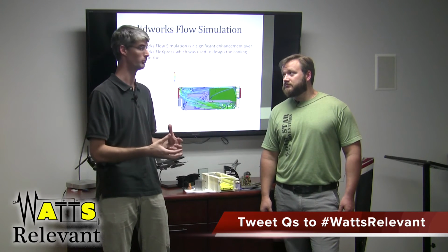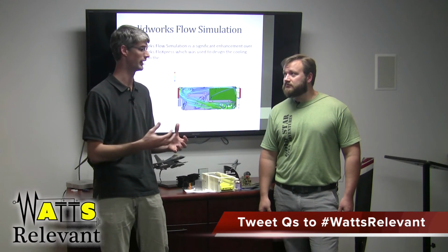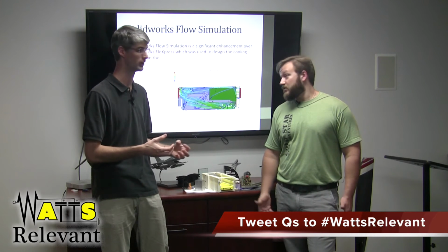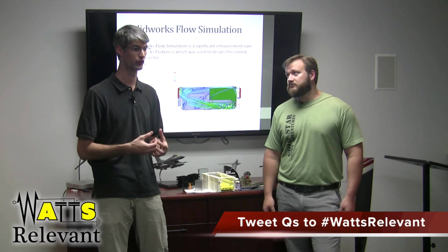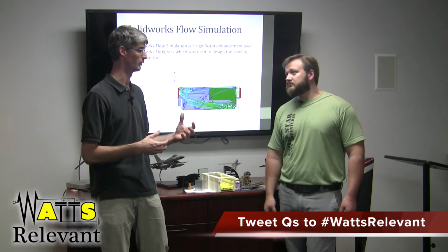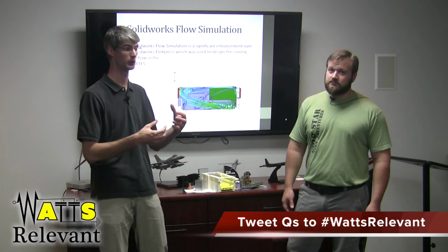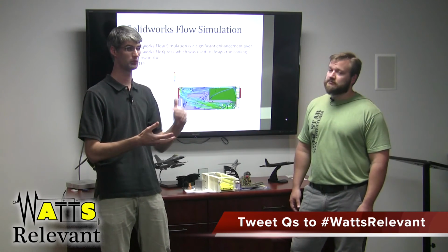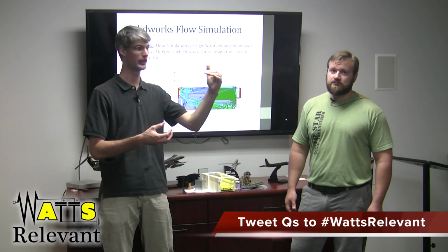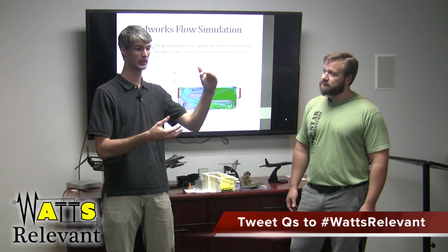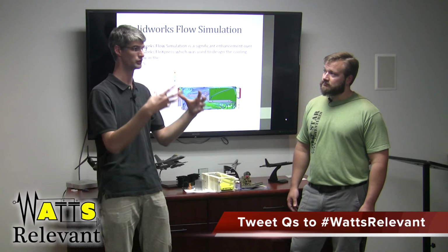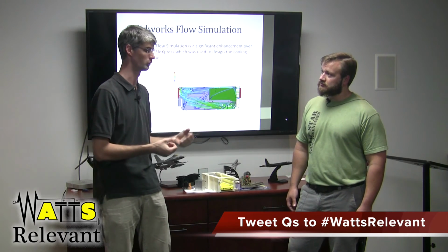It could have different levels of moisture, so I can't necessarily just open that air to flow through my components because I could get condensation or other things. Particularly, this is a big issue for parts that have been on airplanes at altitude. As they come down, they were really cold because the air is really cold, but now they're coming down into warm, moist air, and then just moisture gathers just like it does on your water glass.